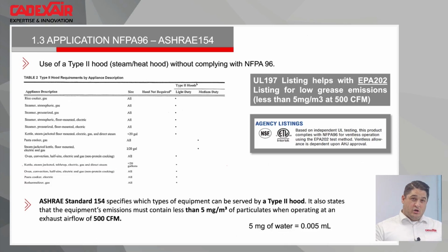But something is sure, I made just a small verification. 5 milligrams of water is 0.005 milliliter inside of 1 cubic meter at 500 CFM. So I will stick with that. I cannot tell you what is listed equipment or not. But now there's a test standard. It's a UL 197 listing with the EPA, a test that will prove that the equipment has a lower emission than the requirement for a Type 2 hood.